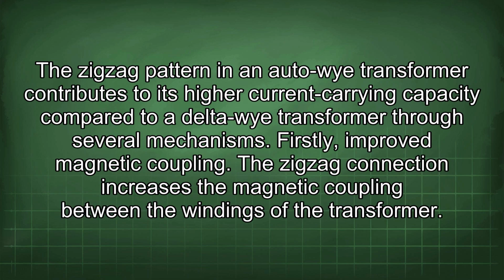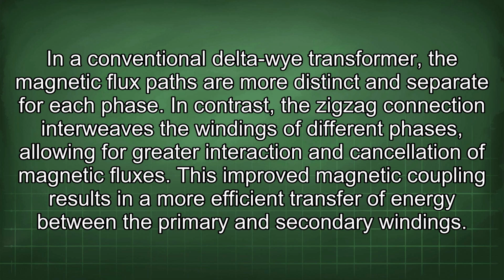The zigzag pattern in an Auto-Wye transformer contributes to its higher current carrying capacity compared to a Delta-Wye transformer through several mechanisms. Firstly, improved magnetic coupling. The zigzag connection increases the magnetic coupling between the windings of the transformer. In a conventional Delta-Wye transformer, the magnetic flux paths are more distinct and separate for each phase. In contrast, the zigzag connection interweaves the windings of different phases, allowing for greater interaction and cancellation of magnetic fluxes. This improved magnetic coupling results in a more efficient transfer of energy between the primary and secondary windings.